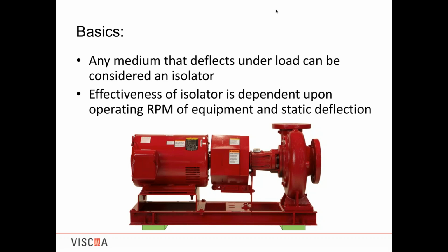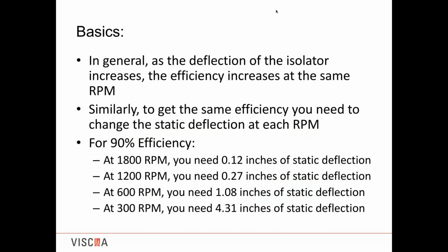Now, in general, as the deflection increases, the efficiency increases at the same RPM. And that gets a little confusing because what's happening is your required deflection becomes inversely proportional to your RPM. So as I have a piece of equipment with higher RPMs, I need less static deflection to get the same efficiency. And it may be counterintuitive at first, but I have a little chart there.